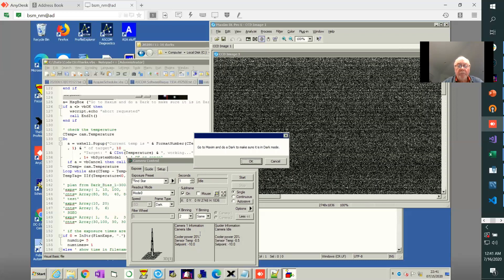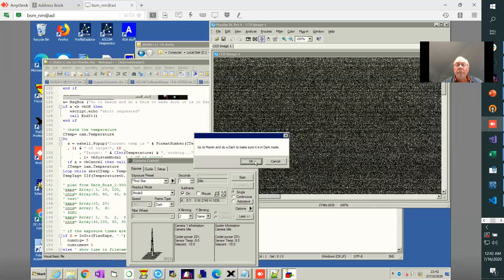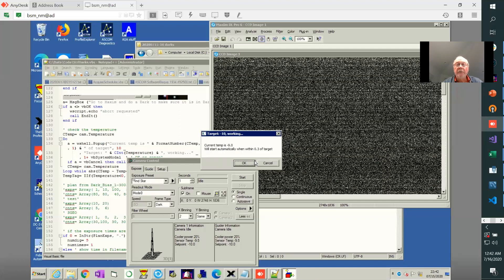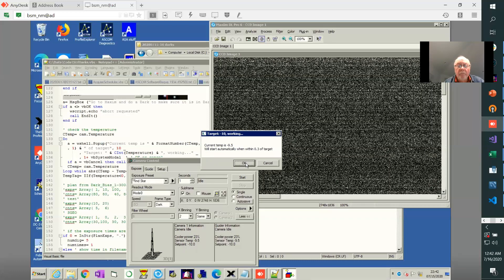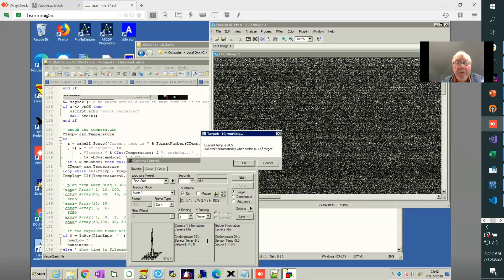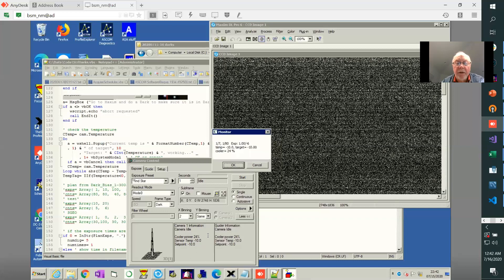Looking at the camera, cooler power is coming up. Temperature is going down. It is going down. So we did this, say yes, current temperature is minus nine, and we're going to start automatically. Let's just sit here for a moment, make sure it's totally stable. Now we're still increasing. We've achieved the minus 10. I'm just looking to see if we have any overshoot. Well, it actually decided that it's ready to start.